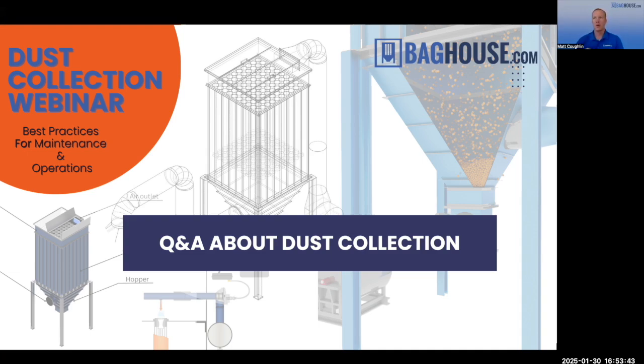There are a lot of other little requirements that you might run into, like duct thickness requirements. You can't have really thin little spiral ducts in combustible dust applications, specifically between your isolation and baghouse. We can help you be compliant with a lot of that stuff. So if you ask us to quote a system with combustible dust, we will probably include in the package a number of options, including the vents, the isolation, and the explosion-proof discharge device. But we will certainly want to have a discussion with you about what specifically your local regulations require so we can make sure we meet those.